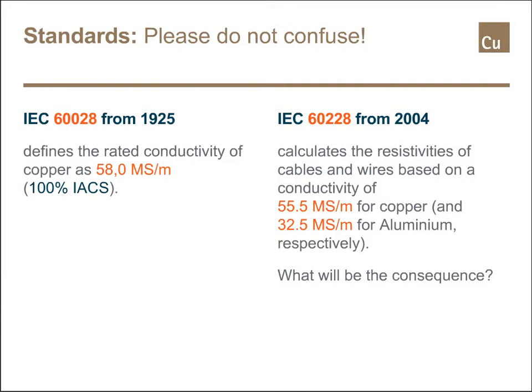That means 1 kilometer of cable of the respective type of cable has a maximum resistance, and these maximum values for each cross-section are calculated with a conductivity of 55.5 megasiemens per meter for copper and 32.5 megasiemens per meter for aluminium conductors. Now, in fact, the conductivity of copper nowadays is 58.5, and then I think you can imagine what the cable manufacturers will do. In fact, a 16 square cable has only 15 square copper in the end, but it serves the same purpose.